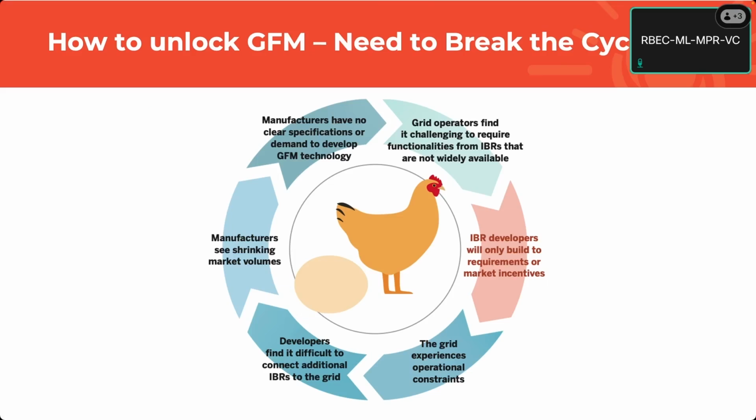You miss out on some of the other advantages like a very strong frequency response, but you don't have to always have that. All of your batteries are not going to be always operating at full discharge or full charge. And so if you're just asking for this capability when you have it, that's essentially the ERCOT approach. They're saying, if you happen to have headroom, we would like you to use it in this way.